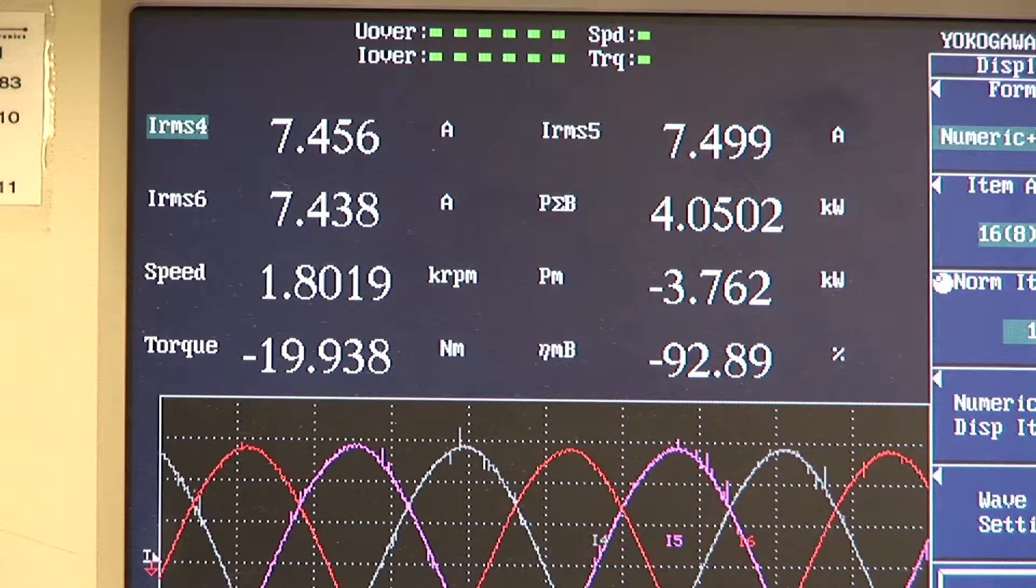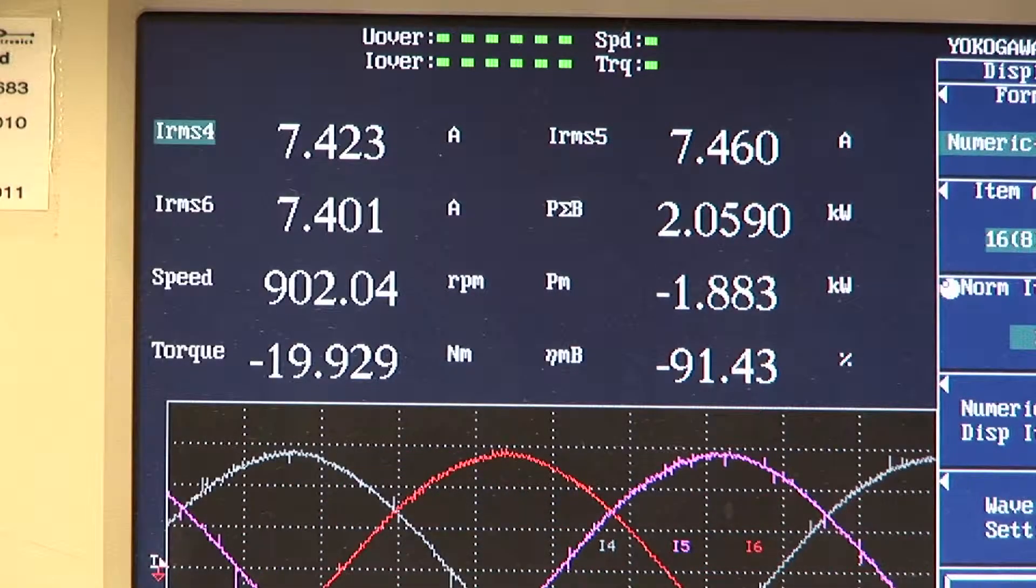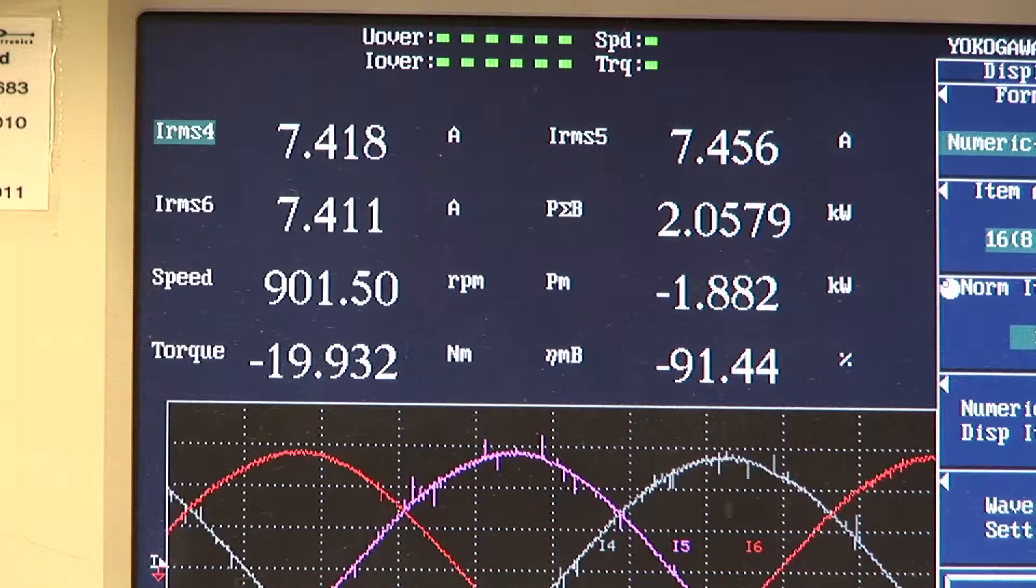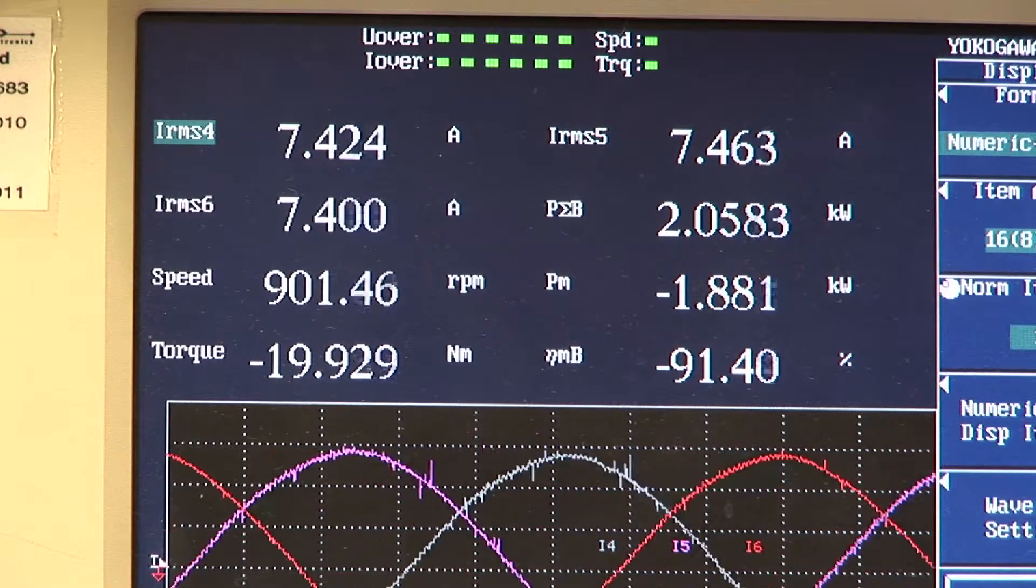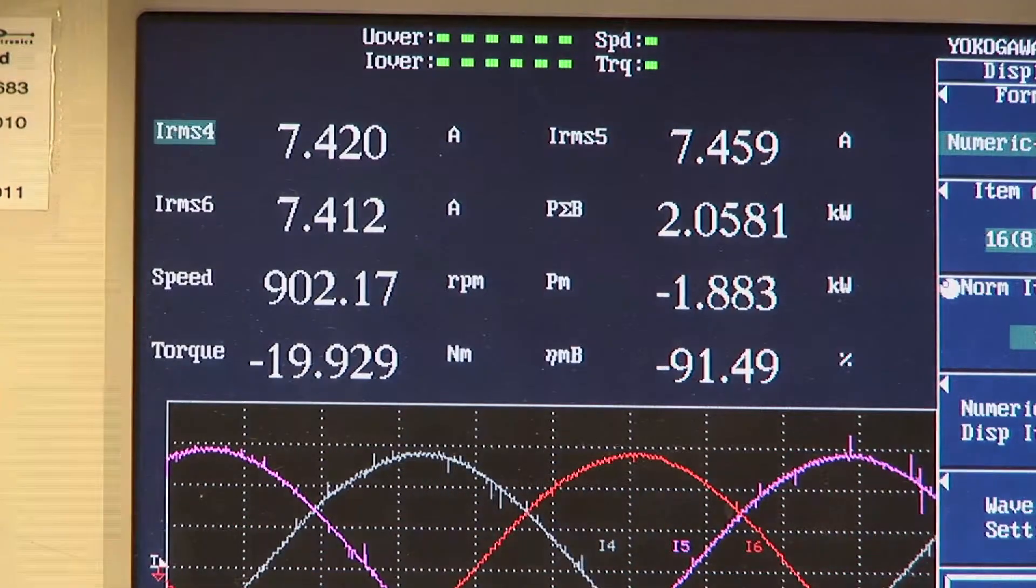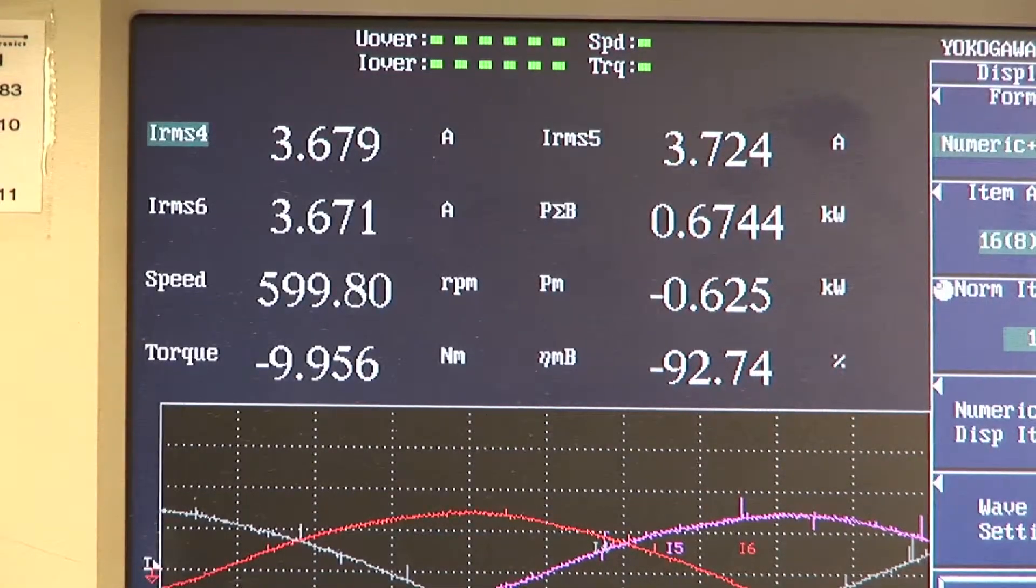We are now operating at half the rated speed, that is 900 rpm, and the torque is 20 Newton meters. We see that motor efficiency is over 91 percent. We will now operate at a reduced torque level at half the rated torque of the motor, that is 10 Newton meters.